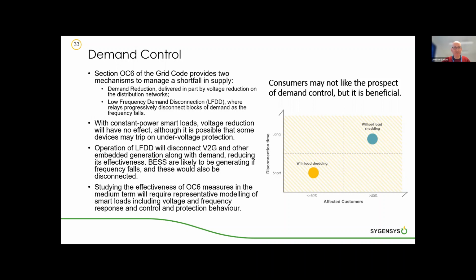With constant power smart loads, voltage reduction will have no effect on their demand, although it's possible that some devices may trip on under voltage protection. And secondly, operation of low frequency demand disconnection will disconnect vehicle to grid generation and other embedded generation along with demand, which will reduce its effectiveness. Specifically, battery energy storage systems are likely to be generating if the frequency has fallen, and these would also be disconnected from the distribution network. So studying the effectiveness of OC6 measures in the medium term will require representative modelling of smart loads, including voltage and frequency response, and control and protection behaviour.